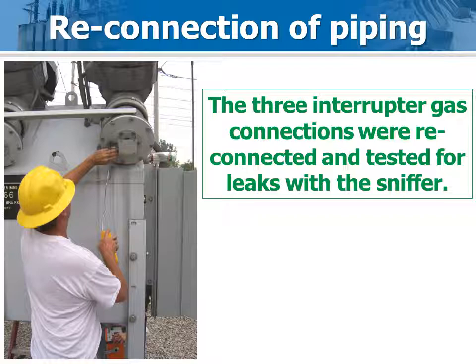Before the piping job was started, the manifold was disconnected from each interrupter. Now that the new piping, new gas fill port, and gas density sensor are installed, the manifold is reconnected to the interrupters and tested for leaks with a sniffer and/or soapy solution.